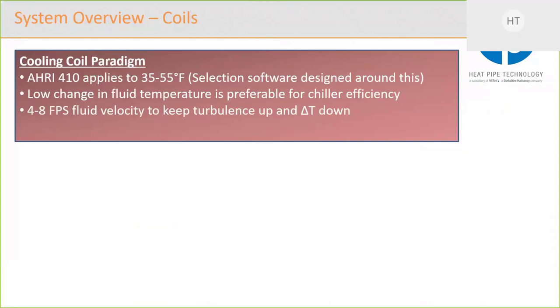And also, as I mentioned, a higher fluid velocity also keeps your fluid delta T down to help with chiller efficiency. And the other aspect of that is that most chilled water coils are still 5/8, even though in many refrigerant applications, coils are going down to 3/8 and these microchannels as well. On water systems, there seems to be resistance to that, and they're still really mostly around 5/8. And the reason for that is, as you need your higher velocity water flow, you go to a smaller pipe diameter and the pressure drop increases massively. So when I say resistance, that is a pun intended.